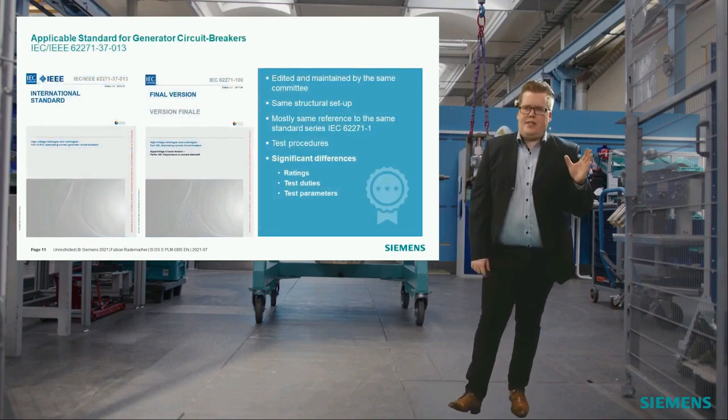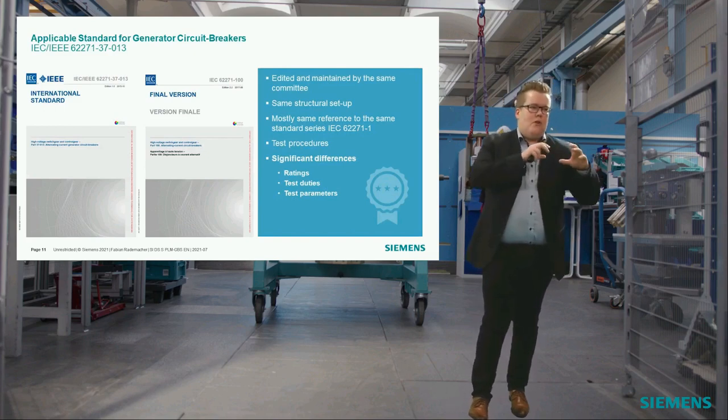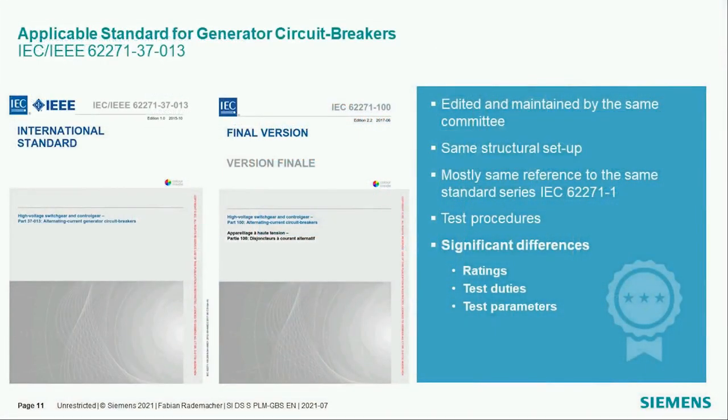What I have highlighted in the last minutes is that we have two major topics of circuit breakers, the IEC circuit breaker and the IEC/IEEE circuit breaker. Back in 2015, the IEC/IEEE committee decided to publish a certain standard which addressed these unique characteristics for the generator circuit breakers. So the IEC 62271-100 is not applicable anymore for generator circuit breakers because it does not deal with the delayed current zero, the transient recovery voltage, or the rate of rise of recovery voltage.